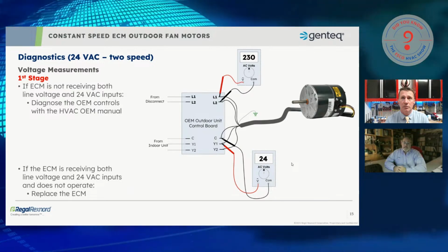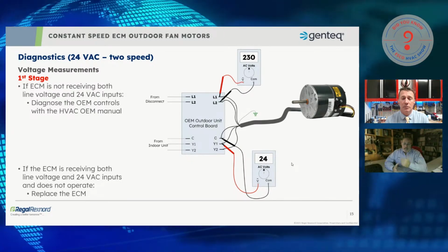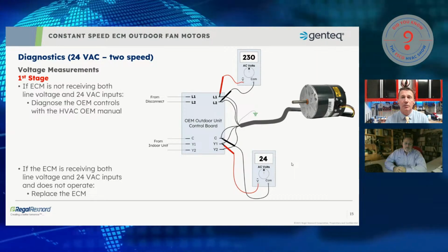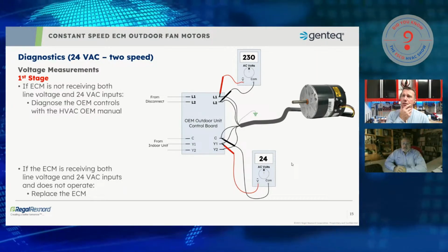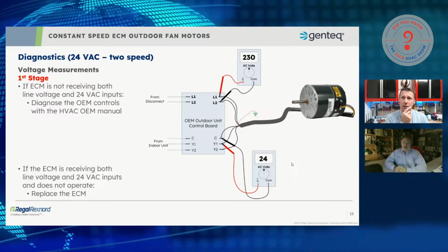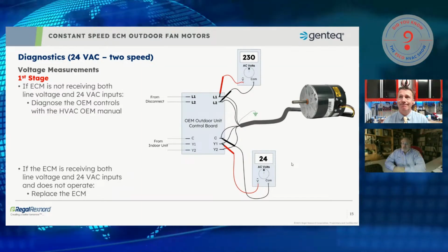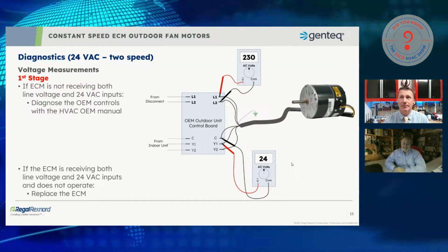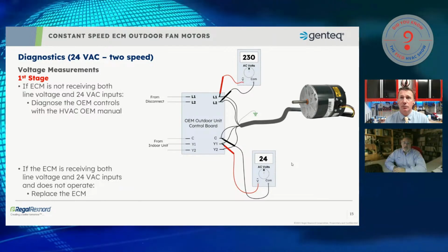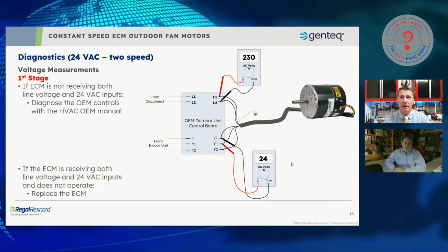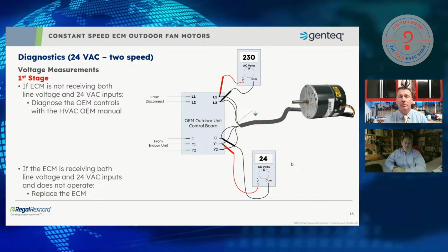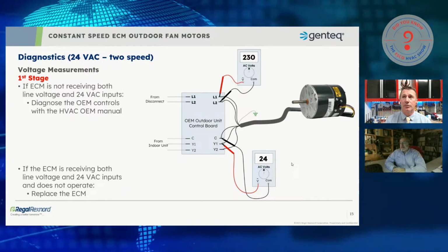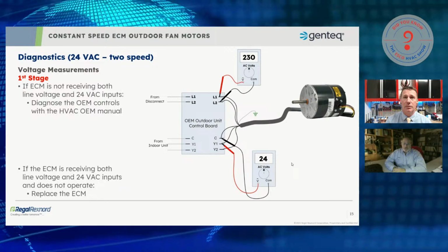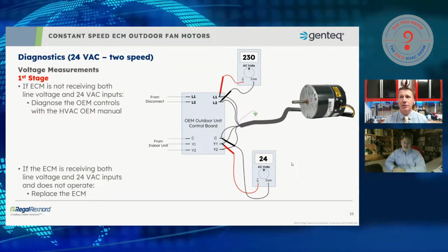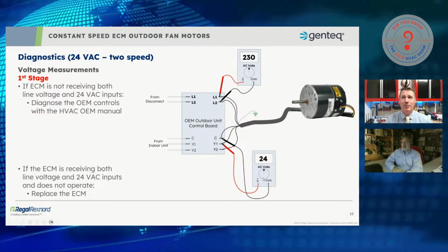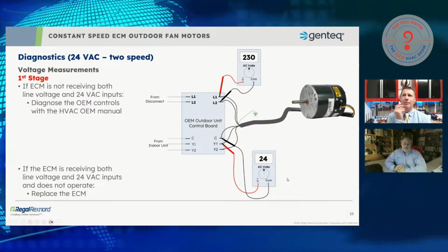If it doesn't work on one speed, that's going to be a problem, unless you're going to lock the system into second stage its whole life and wait for that second speed to fail, which is a question I have been asked. Well, what if my first stage speed doesn't work, but my second stage speed does? Can I lock it into Y2 and leave it that way until I can come back and get cooling? Absolutely. If your second speed works, that's not a problem. But keep in mind, that's probably not a good long-term solution. No, it's temporary for sure. Definitely a temporary solution.